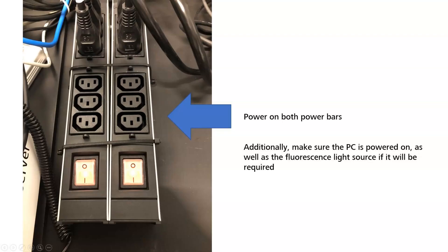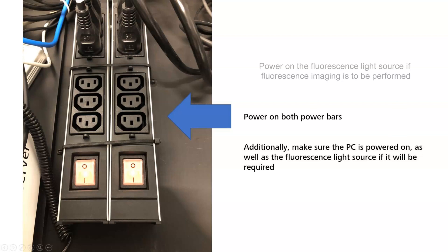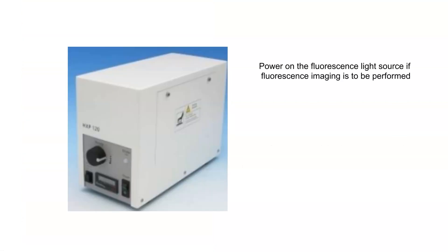To begin the operation of the Palm system, turn on the associated computer and components. The order of powering up the system does not matter, however all components should be powered on prior to starting the software. The fluorescence illumination may be powered independent of other components. If fluorescence imaging is to be done, be sure to power on the fluorescence light source.